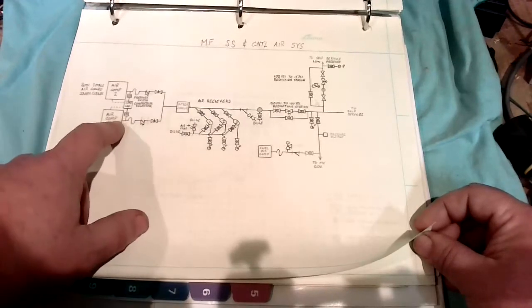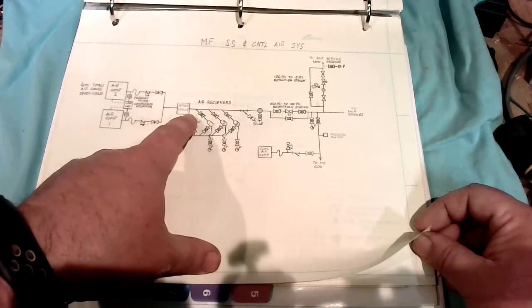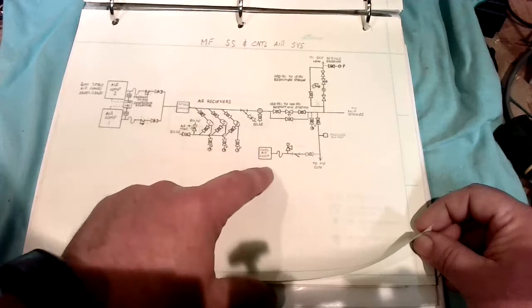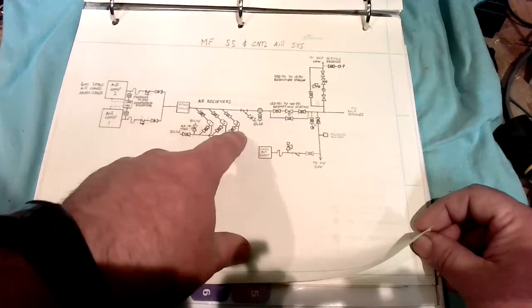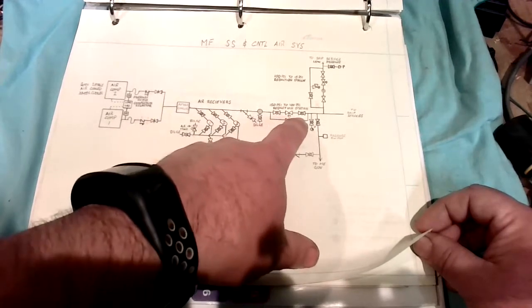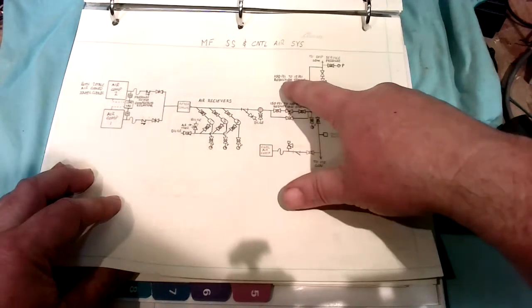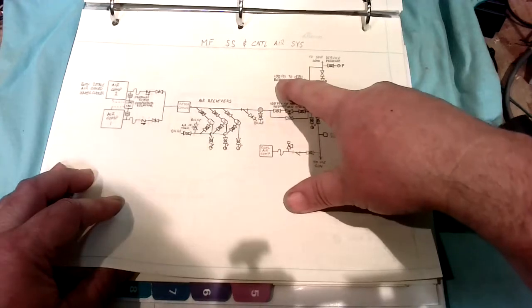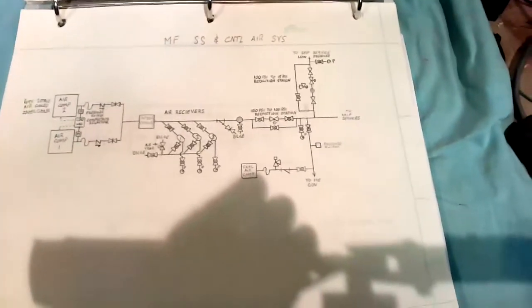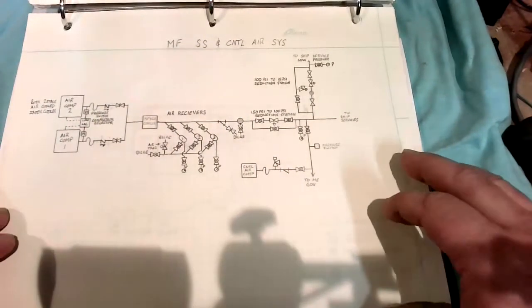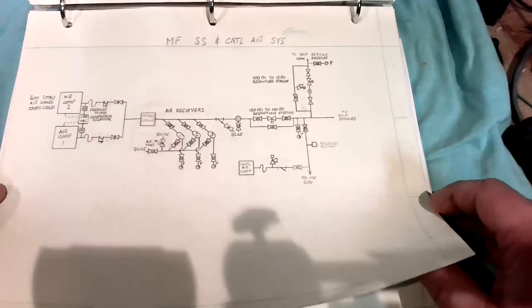We got two air compressors. We got lead lag control, a cooler so we can cool the air, get a better charge out of it, and we just keep going on. So we got different air receivers here, a reduction station, reducing down from 150 psi to 100 psi, and then another reduction station from 100 psi down to 15. And got a pressure switch to say, hey, we need to start the compressor and everything else.